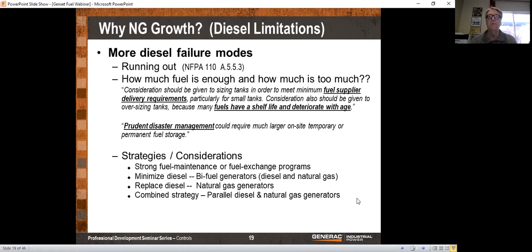Running out is another problem. If you have lots of diesel fuel, you have to maintain that diesel fuel. That drives up the cost. If you have little diesel fuel, then of course you're going to run out more quickly. If you have to have pumps and so on, you've got a day tank outside and you've got solenoid valves and transfer pumps, then there's lots of things in there that add to the failure modes that you don't see when you just go to the natural gas utility. You hook up to the utility, that's all their problem to keep that gas there, and it just goes straight from their system to yours.